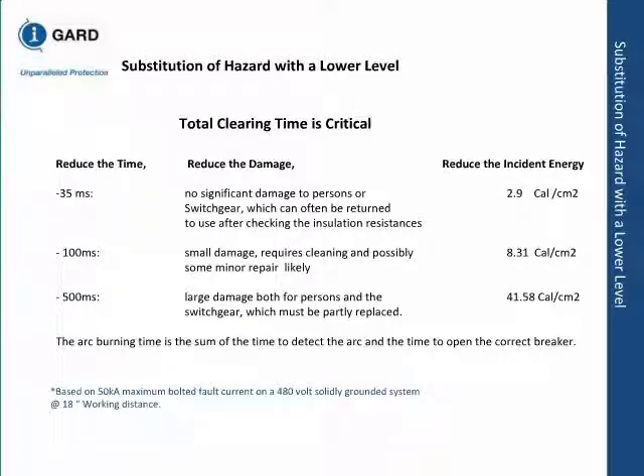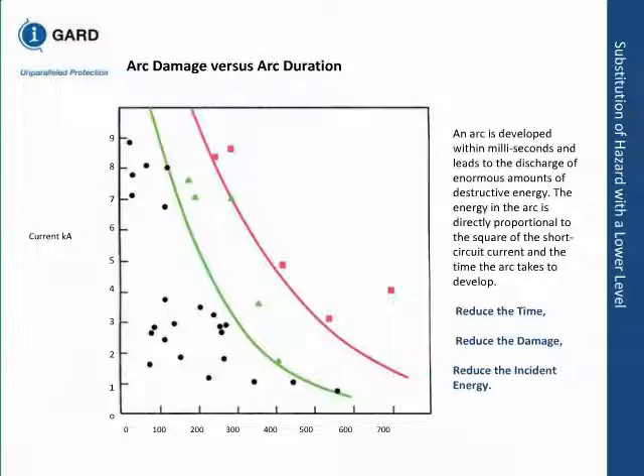This is showing you 2 curves. Anything you can interrupt before the green line will have minimal damage. Anything above the red line is going to be tremendous damage. You can notice all of them are based on how fast you clear. The horizontal axis is time, and the vertical axis is current in thousands of amperes. So if you can clear the fault quickly, that is one technology. If you cannot reduce the fault current, you cut down the time to clear it.